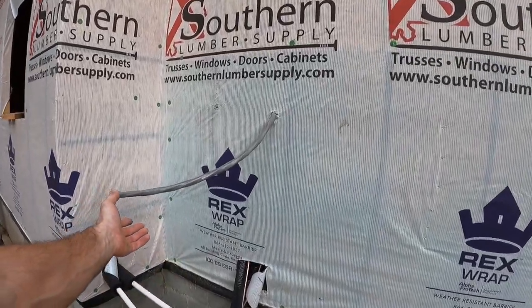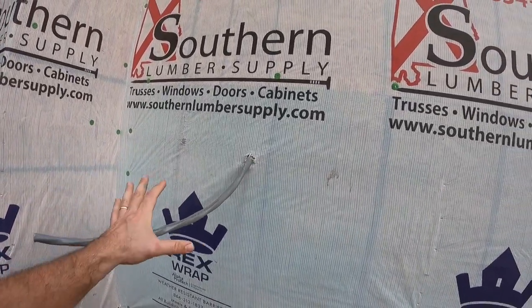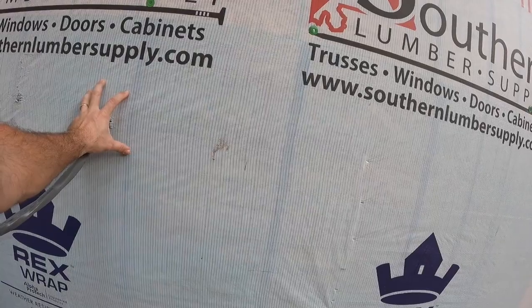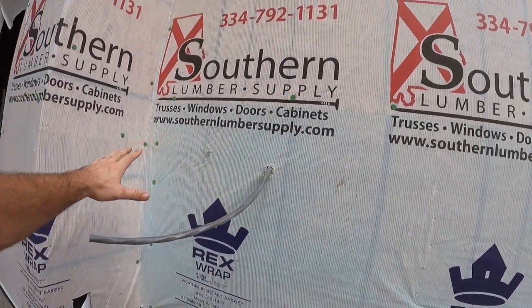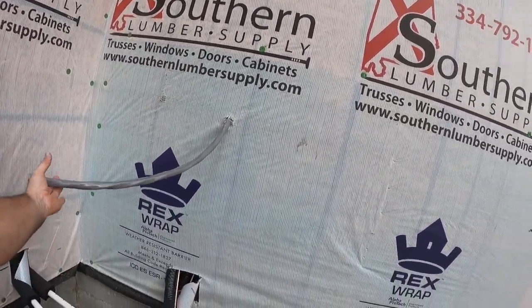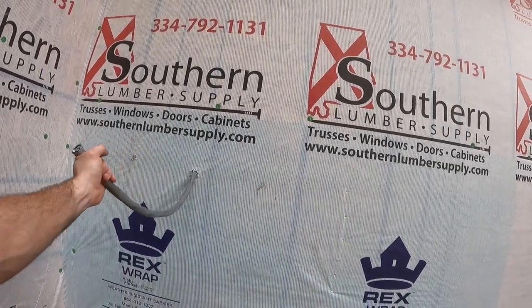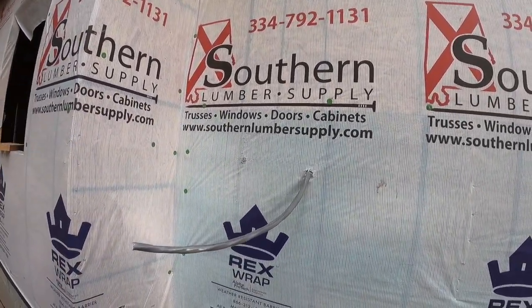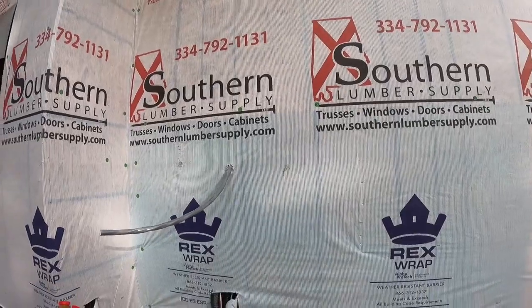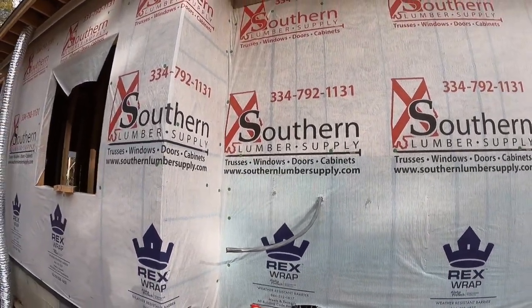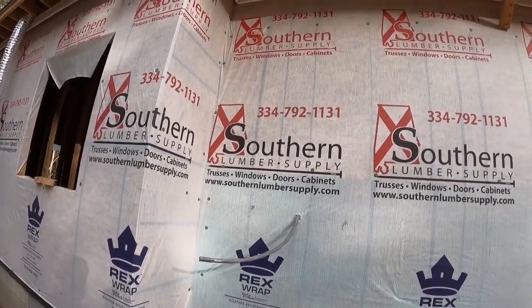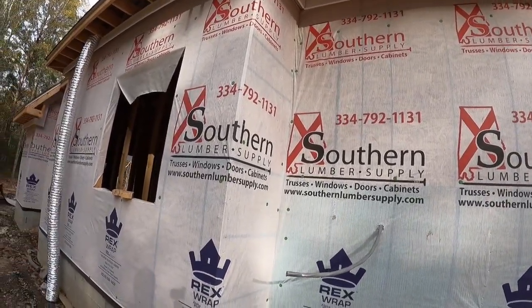I'll go back in and show you how the electricals run, but we'll have another panel here similar to the one upstairs, what I call a split panel. We're just going to take 100 amp wire and split it into, I believe one of these condensers is a 40 amp, one's a 30. So there'll be a 2-pole 40, 2-pole 30, or a 50 and a 30 out here.